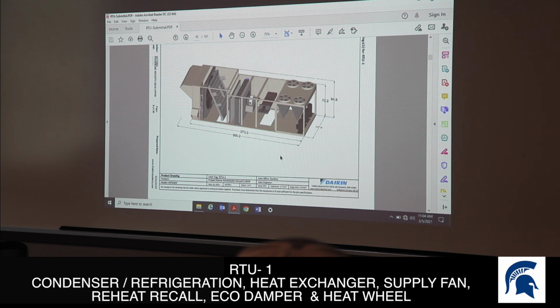This happens to be RTU1. You've got a condensing section here where the refrigeration system is, a heating section here where your heat exchanger is shown, and this is your supply fan. This is the DX cooling coil and the hot gas reheat coil, which we'll talk about. You've got a set of economizer dampers that decide the outside air and return air combination, and you've got your heat wheel here.